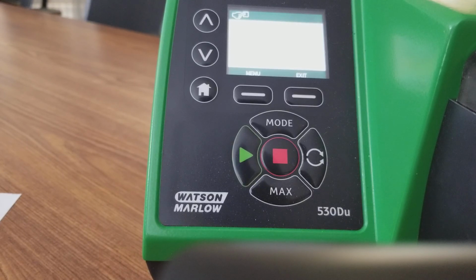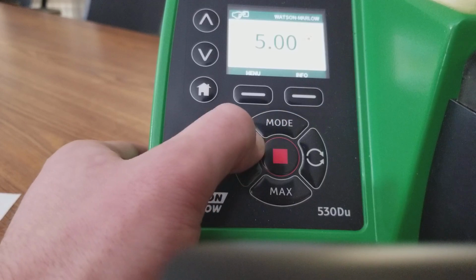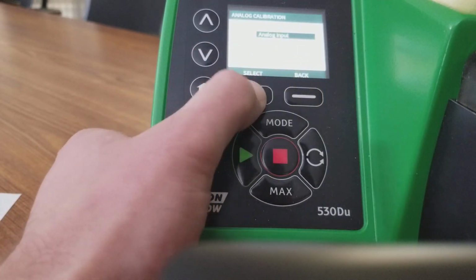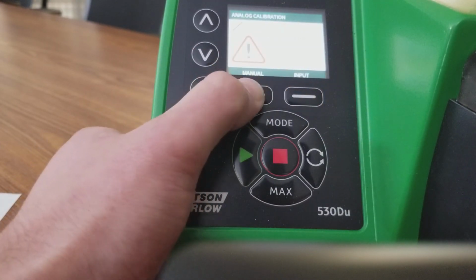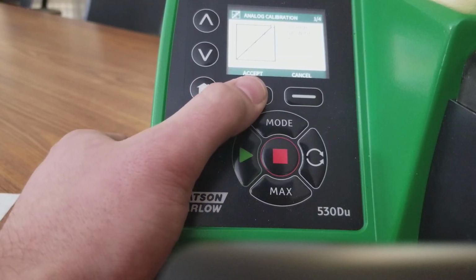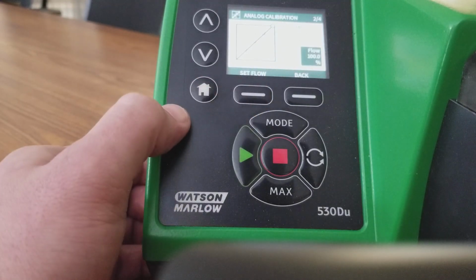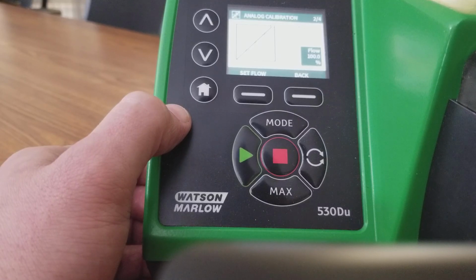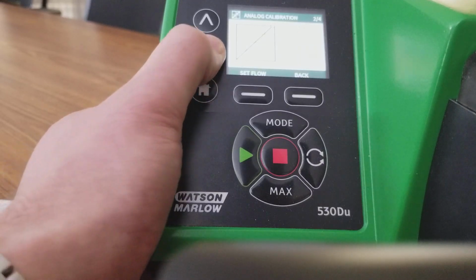So we take 179.2 divided by the 220 RPM multiplied by 100 to figure out our percent. So then it comes out to 81.45%. And why this was important is because if you remember when we were in our analog and we had that manual option at 20 milliamps, there's our percentage. To figure out the percentage is basically knowing what your RPM was at whatever set point you had, divided by the 220, multiplied by 100 to give us a percent.